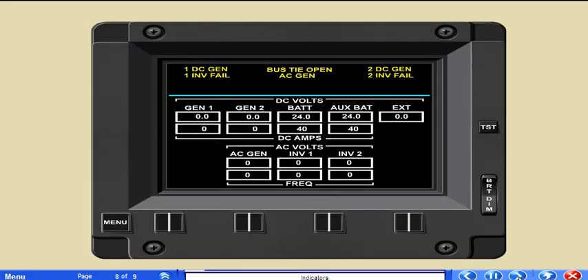Switching on certain DC equipment when the battery is the only source of DC power can sometimes cause the bus tie contactor to close momentarily. The bus tie open, door open, or other caution lights flashing may indicate this transient condition. Also, the instruments powered by the DC primary bus may flicker.